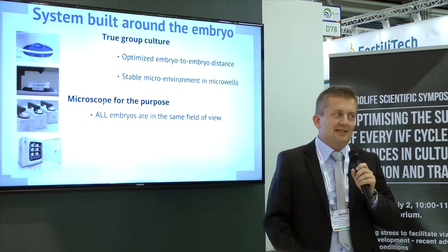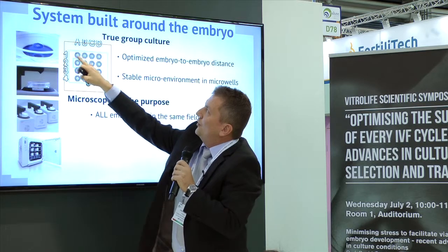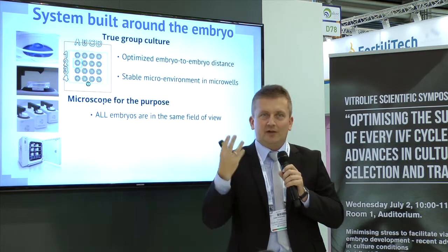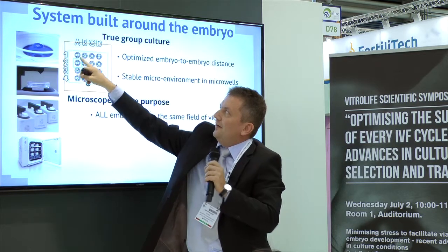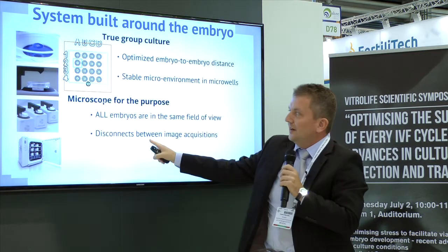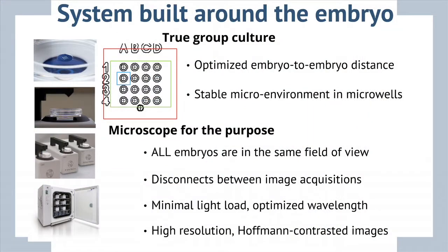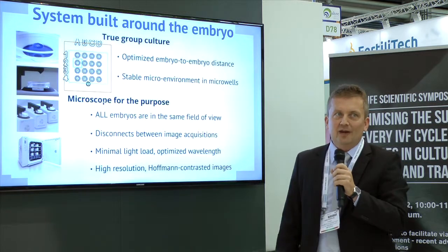About the microscopes: one of the innovations is that it has a very large field of view. All the microwells are within the same field of view, meaning nothing has to be moved during embryo culture — they are sitting still, and with one image we are imaging all of them. The microscopes are only switched on during image acquisition, for the milliseconds of imaging, and switched off outside of that, eliminating almost all electric effects. The light load is practically zero since it is a digital technology, and the contrast is Hoffman contrast so we can see not just kinetics but proper morphology on the microscopic images.